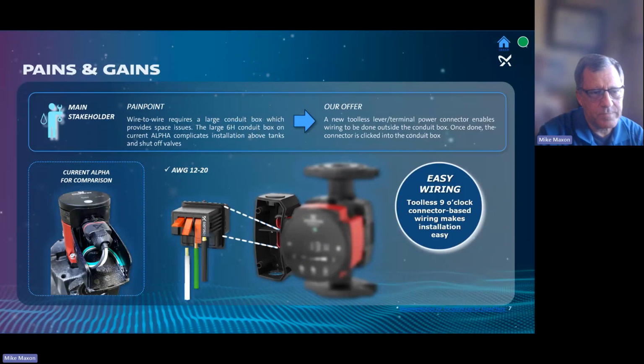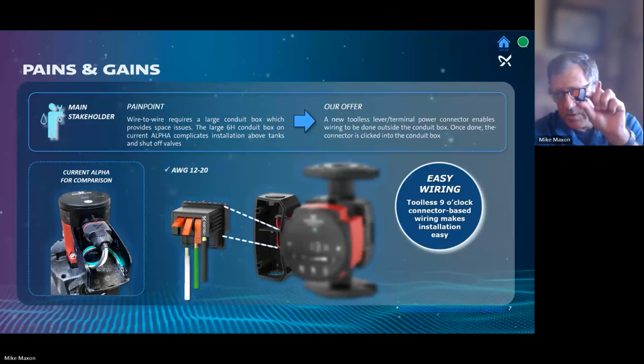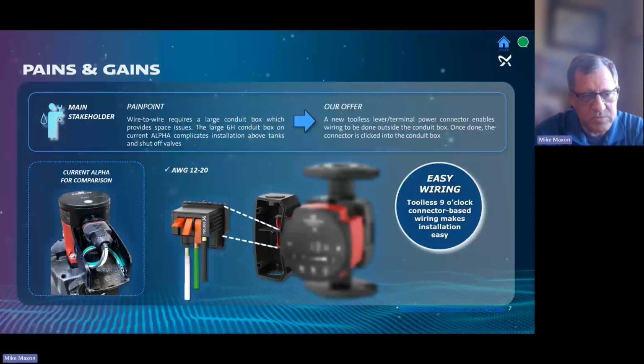The ease of wiring. This is really a pretty good wiring system. I've talked to a lot of guys that have put in pumps and they really like this. You run your wires up through the hole. This block will come in a bag separate with the pump. And you just run the wires through the hole, and the toolless levers here are able to be picked up. You plug the wires in, you lock them back down with your finger, and then you just plug into the pump, and it's wired. So you're able to do all the wiring out in space outside of the box.